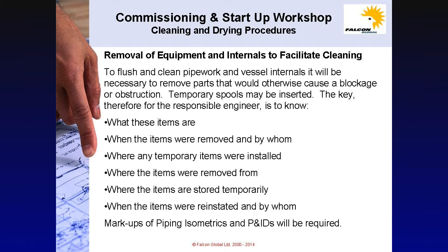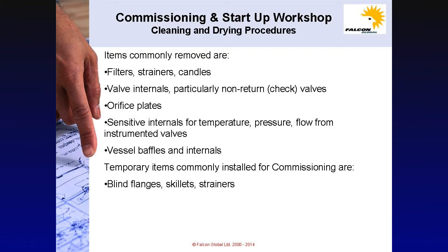The key, therefore, for the responsible engineer is to know what these items are, when the items were removed and by whom, where any temporary items were installed, where the items were removed from, where the items are stored temporarily, and when the items were reinstated, by whom. All of this will need to be shown on markups of piping isometrics and P&IDs.